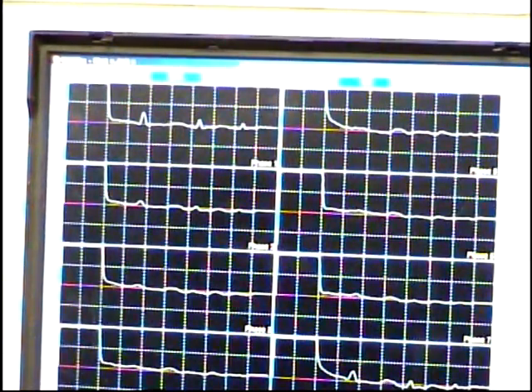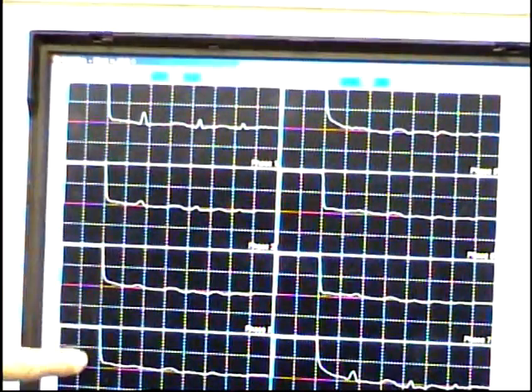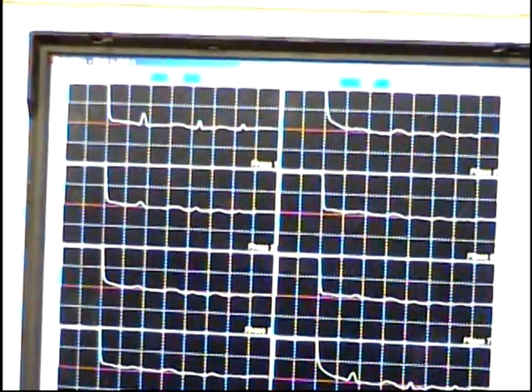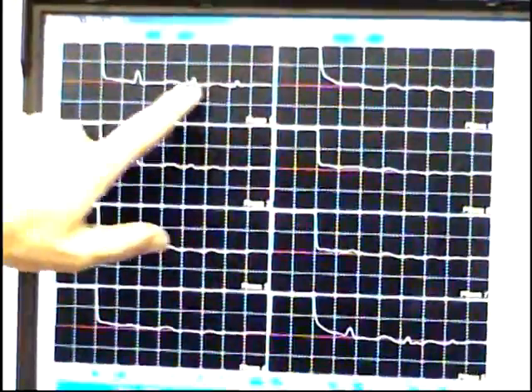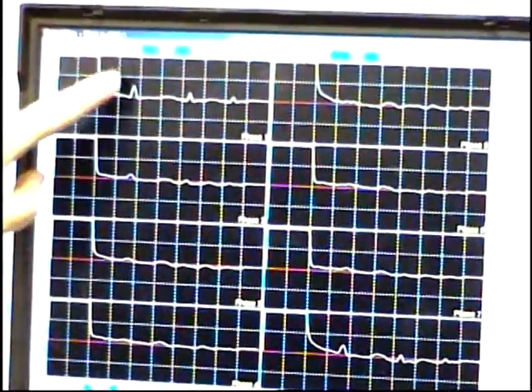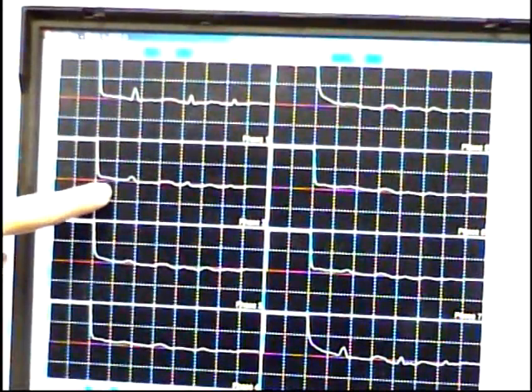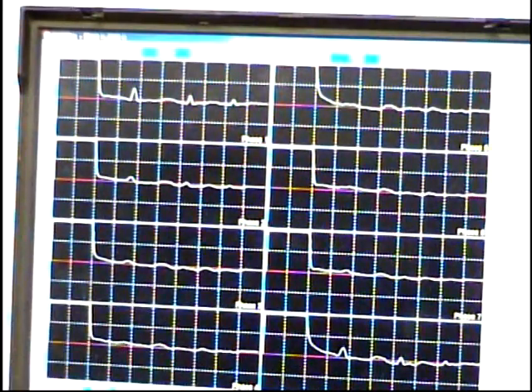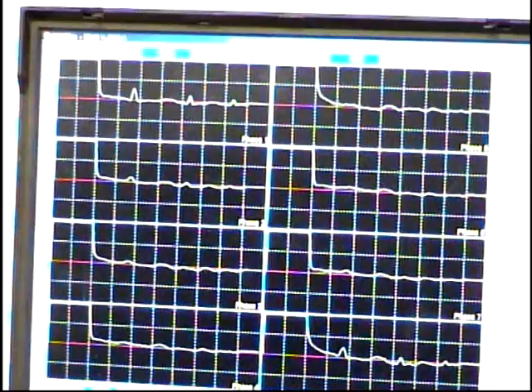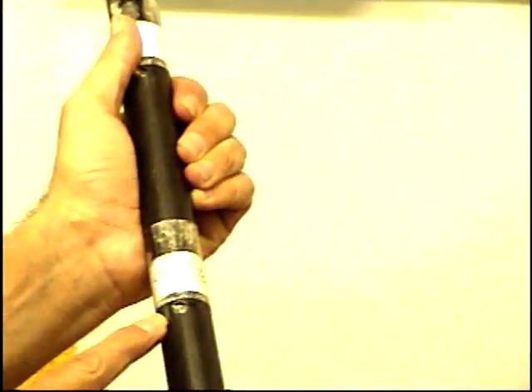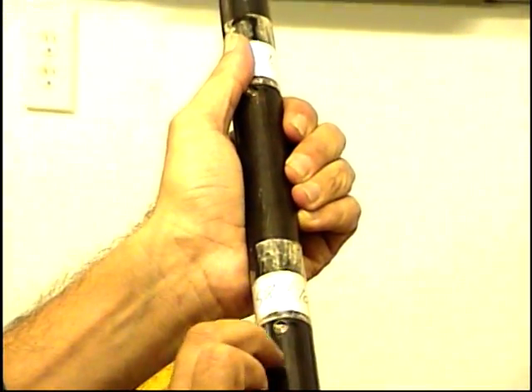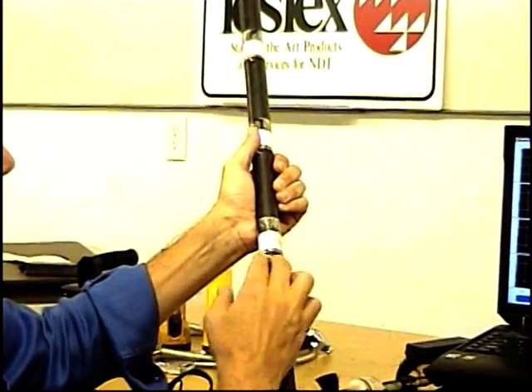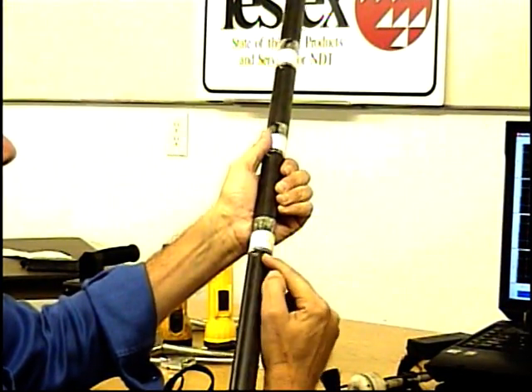Hit my F4. Back to the 8 channels, because we have 8 channels in our probe. You're going to see the 3 pits in the first channel, second channel, and in the last channel. You notice the middle channels, it doesn't show up too much. So what that's telling you is when that probe was being pulled through, you had the first channel here, the second channel, and part of the 8th channel coming around.